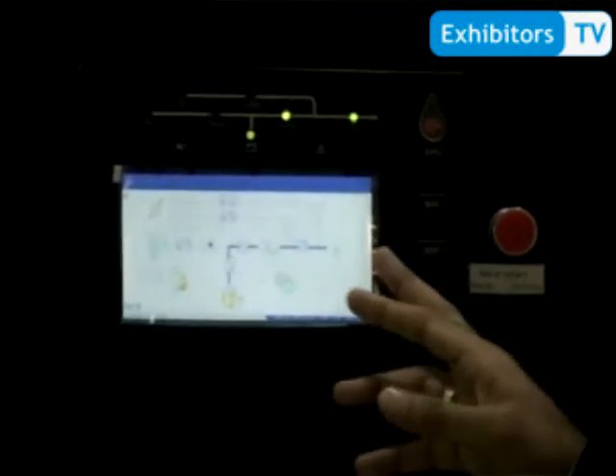The system has a panel on it, and it can be programmed so that when solar is coming in, it charges the batteries and powers the load. When solar isn't available, the load runs on the batteries, like it is right now. When the battery gets low, it automatically switches over to the mains, and if the mains or grid is not available, it starts the generator and switches over to that. The switching between energy sources is seamless, with 0.00 switching time.